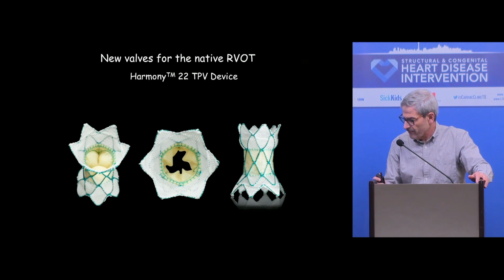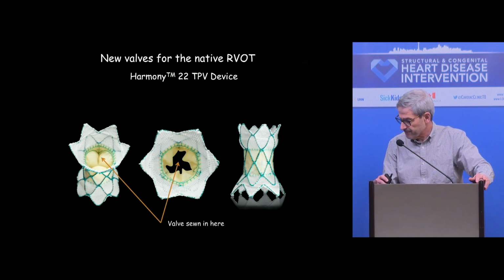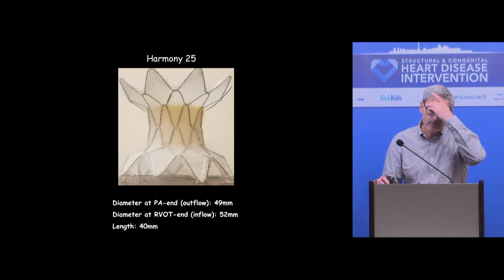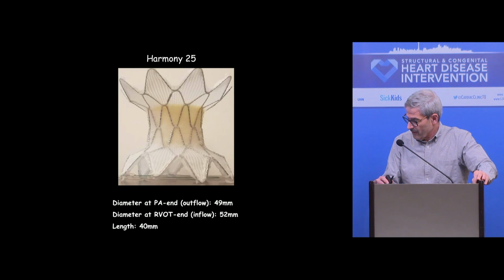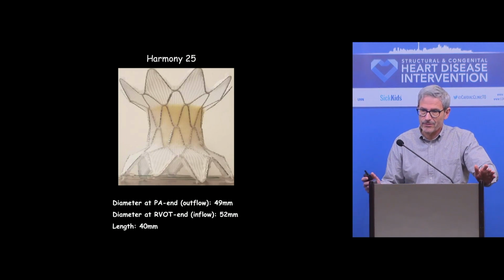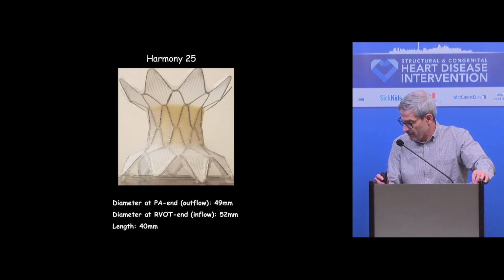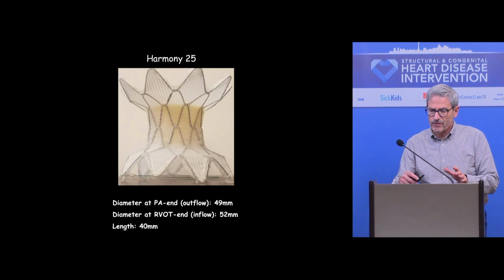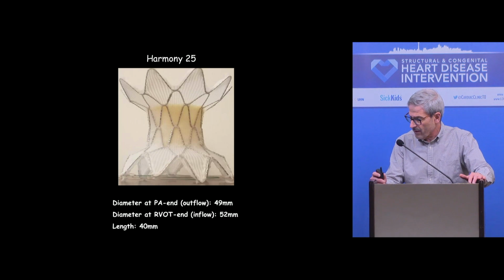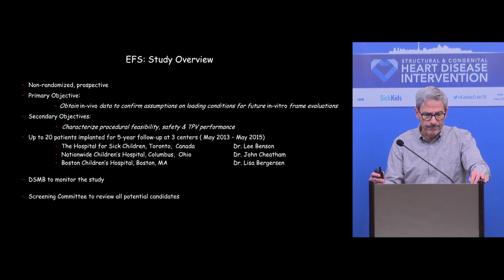This is a more detailed picture of the construction of how the valve is sewn into the chamber, or the middle part of the implant. There is now a larger size valve called the Harmony 25 because the valve diameter is 25, and its dimensions are slightly different. The distal PA end is 49 millimeters in diameter, and the proximal inflow is 52 millimeters, which allows you then to apply this to a larger cohort of patients for implant with larger patulous outflow tracts.